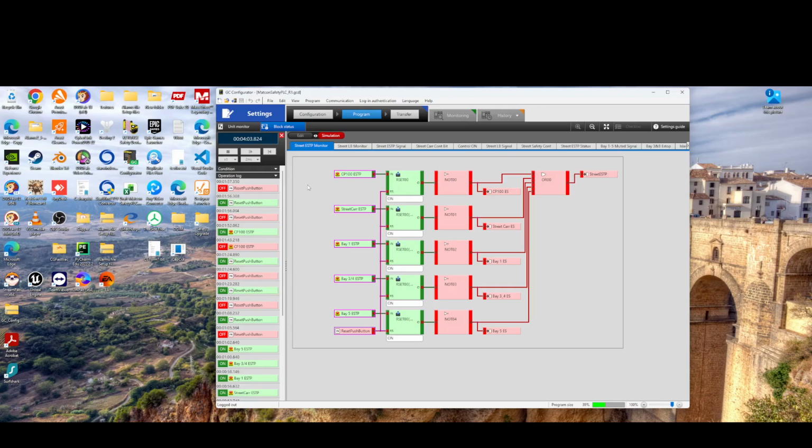The second thing that I want to make you aware of, and I'll show you this right now, is you saw that I just reset this with the reset push button. It only works on the screen that you're on at the time. And what that means is that this isn't like the PLC where it's running this block and then straight into this block and straight into this block many times a second.